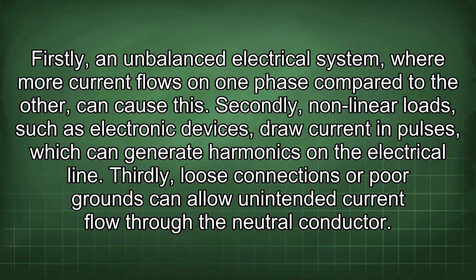Firstly, an unbalanced electrical system where more current flows on one phase compared to the other can cause this. Secondly, nonlinear loads, such as electronic devices, draw current in pulses, which can generate harmonics on the electrical line. Thirdly, loose connections or poor grounds can allow unintended current flow through the neutral conductor.